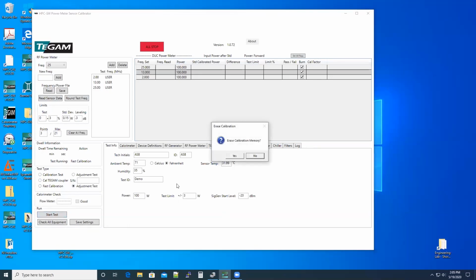First thing it asks is, do you want to erase the calibration memory in the sensor? You have to do that if you're going to realign it. And yes, that is risky. And yes, I do have a backup copy of the data that I can write back in case anything goes wrong. In fact, when the test is over, I'll show you where that button is.